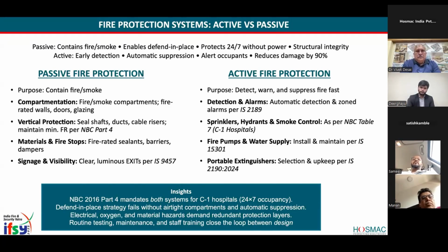So what we do normally for all the facades and especially the windows is we have curtain sprinklers, glass curtain sprinklers. Whenever the fire is caught and smoke is spread, the fire alarm gives a signal to the deluge valve, and the deluge valve is connected to this glass curtain sprinkler. As the name indicates, it will form a curtain of water over the glass, like a water fountain, and it will cool the glass so that it does not break due to the heat. Got that. Yeah. Thank you.